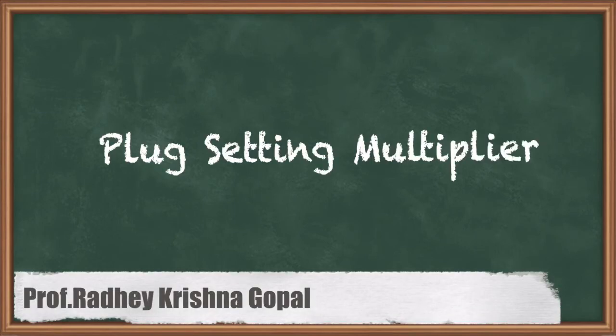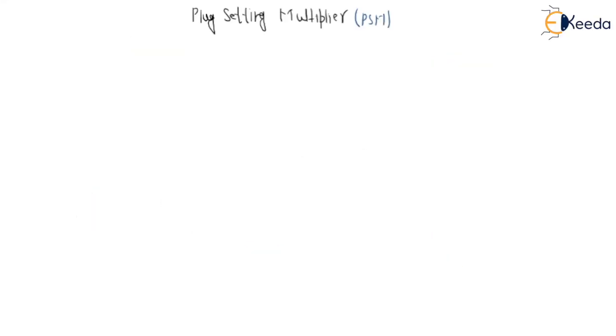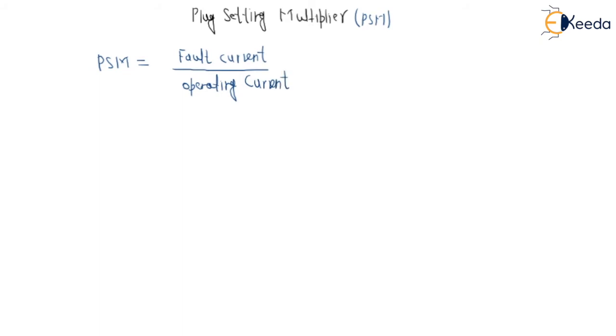We are studying Plug Setting Multiplier, also known as PSM. PSM is the ratio of fault current to relay operating current. For example, if PSM is equal to 10, it means fault current is 10 times more than the relay operating current.